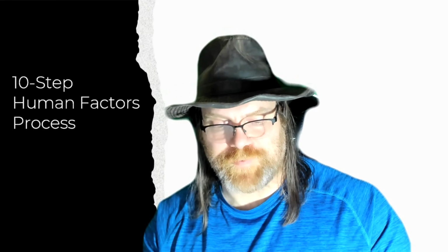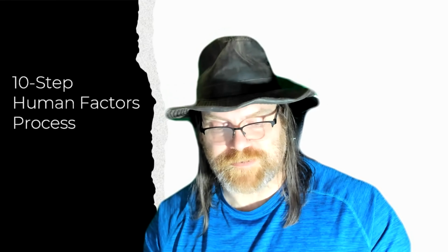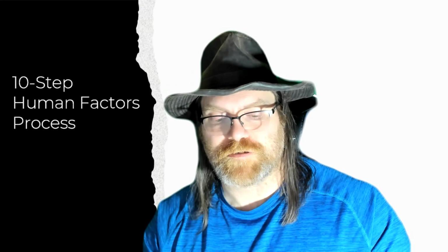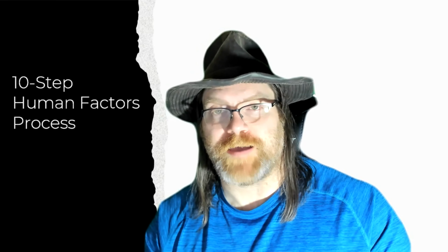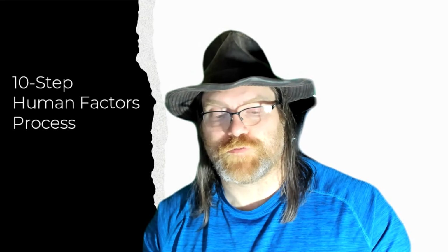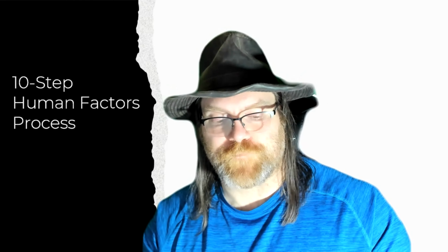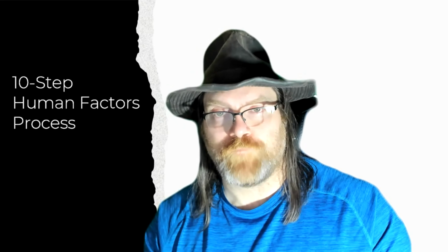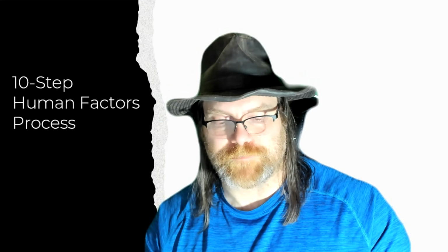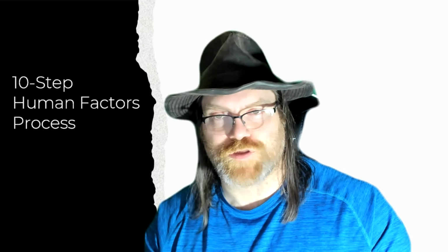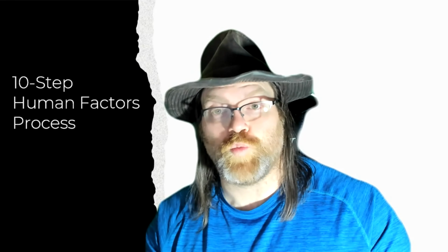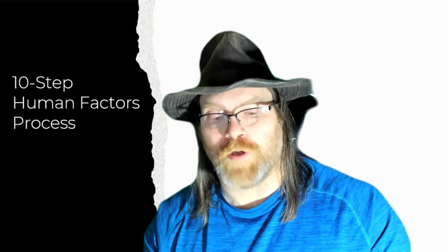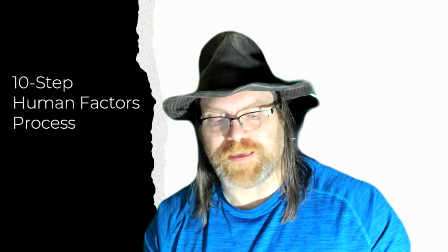Step, I think we're at 6 now, formative testing. This covers clauses 5.7.2 and 5.8 in the 62366 standard. For formative testing, I'm going to give you some guidelines. So number 1, there are no formal requirements for formative testing. It's an iterative process. So formative testing is not something you do once. It's something you typically do multiple times to look at different things.